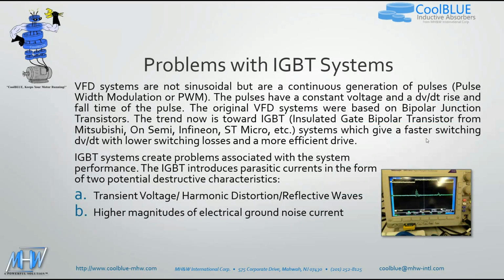VFD systems are not sinusoidal, but are a continuous generation of pulses, as you saw on the previous slide. The pulses have a constant voltage and a dV/dt rise and a fall time of the pulse. The original VFD systems were based upon what they call a bipolar junction transistor, which were slower, and you had the effect, but it wasn't that bad, and it didn't really affect a lot of the motors because of the slow transition times. But now that the VFDs use what they call an IGBT, which is an insulated gate bipolar transistor, the systems have a faster switching time, a faster dV/dt, which does give you lower switching losses and a more efficient drive, but it creates problems associated with the system's performance.